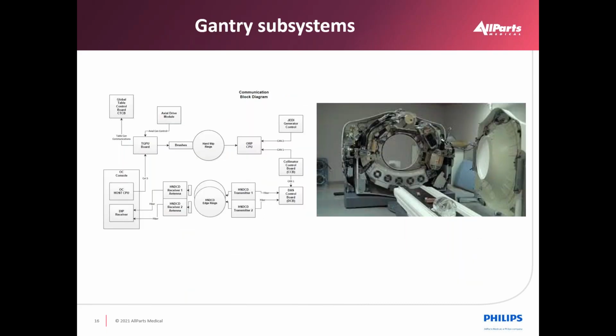So represented here is the gantry that we have at the AllParts office, a GE VCT. And then you see more of the communications diagram listed from that hardware that you saw on the prior slide. So we have the host computer that will send commands over Ethernet to the TGPU. The TGPU will then split those commands into functions appropriate for the table and the axial rotation, and also pass commands through communications over the brushes to the onboard rotating processor computer, which will then split into X-ray control and collimator control, and then eventually to DAS control: the number of views we're going to sample, the type of sampling mode we're going to be in, the aperture size, as well as the beam control for the collimator.